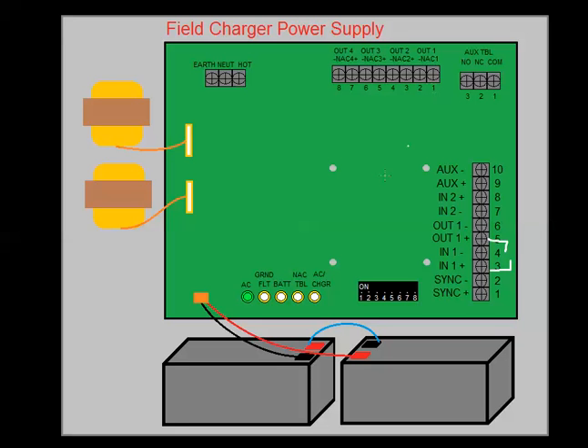The batteries have proper voltage and the charger's not in trouble. So they have their own batteries. They have primary and secondary power. I already said ground faults. So basically if any trouble condition occurs, that's going to open up. There's trouble contacts at the top too, but these do different things depending on these dip switch settings. So we're not going to get into that right now.